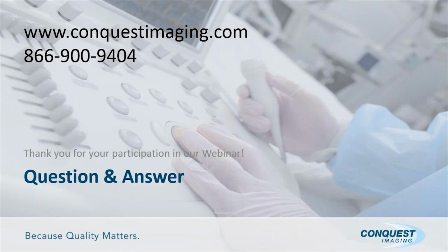Great, thank you. What is the best way to review the NFPA 99 standard? Well, that's an interesting question. Obviously, you can go right out to the NFPA website and look up NFPA 99, which addresses the medical devices, and they have a free PDF that you can review as long as you become a member, which is no cost, as I recall. If there is a cost, it's minimal. The other thing is they have a handbook, if you will, that you can purchase, and it's a little costly, I think $170. But what I like about that over just the NFPA guideline itself is that it specifically tells you what changes have been made. So if from 2012 to 2015 a change is made, it highlights it in addition to just showing you the entire regulation.